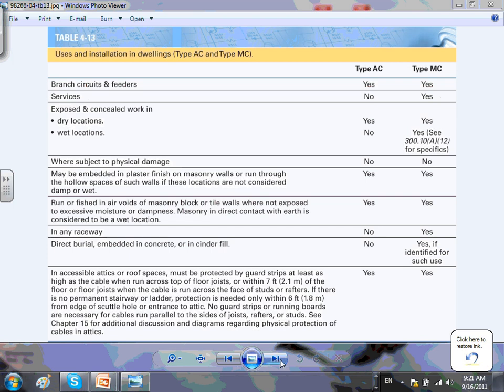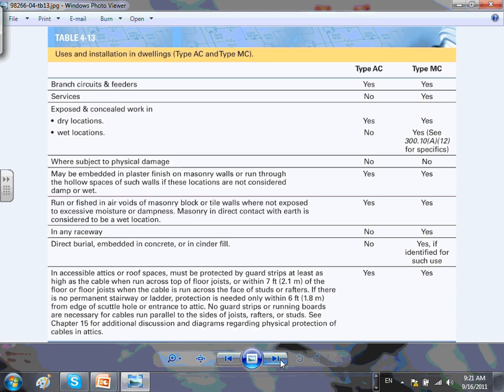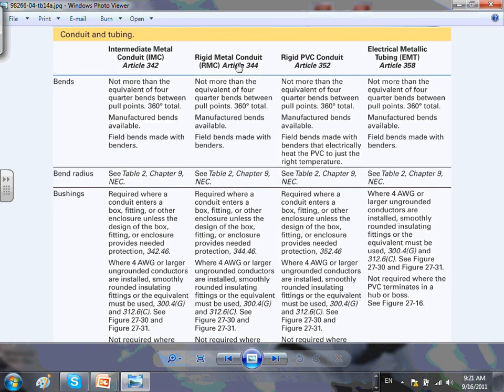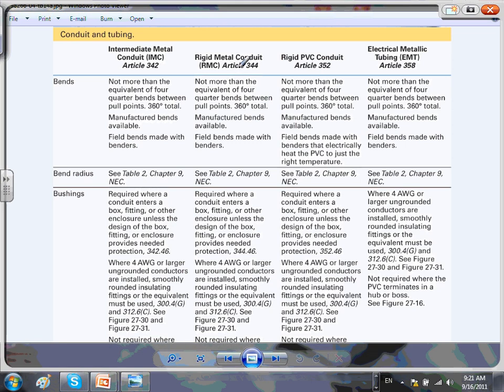Why do they insulate the ground in MC cable? It's better shielding, less interference, and it's safer when you work around it. Have you ever opened a panel where all the grounds are bare? Your chances of that bare conductor touching something hot are higher. So there are safety factors. That would be my two cents on that.